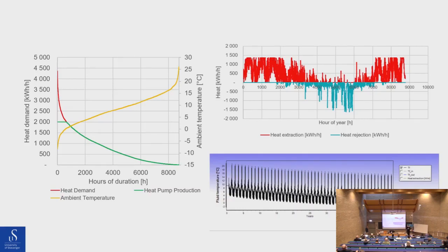I think it's really amazing that by putting down about 100 liters per second of a brine of ethanol mixed with water, you put down 0 degrees water, you extract heat, and you heat the water 3 degrees. So by heating that water from 0 to 3 degrees, you get 70% of the energy demand at campus. So you don't really need the high temperatures in the building heating and cooling systems.